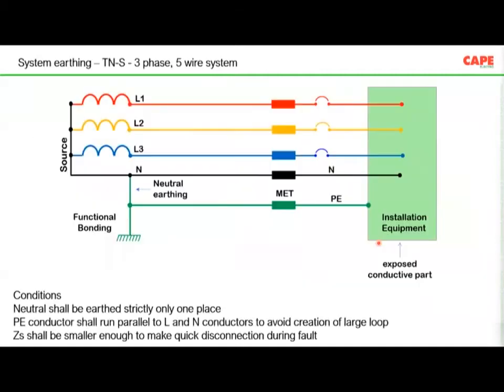So with this understanding, I'm showing you a picture which is a TNS system. I'm sure those who are attending are engineers with a medical background, and they know how the system is implemented in a typical hospital. What I am showing is a TNS system, meaning you have a source. The source can be a DG or a transformer. You have the 3 phases coming from the transformer. You have the neutral, which is also distributed into your electrical installation. Now, what you should understand is, in the picture, the green wire of the electrical installation is connected back to the neutral of the source. So this is a TNS system.